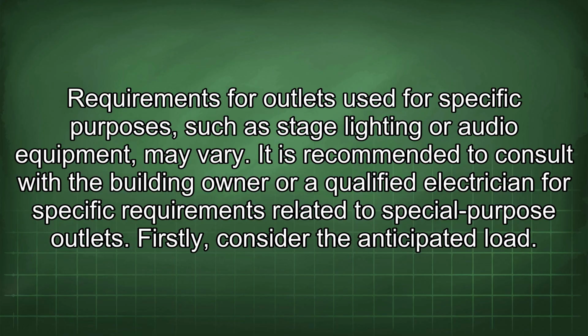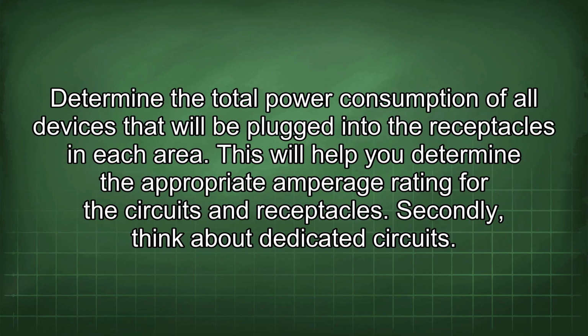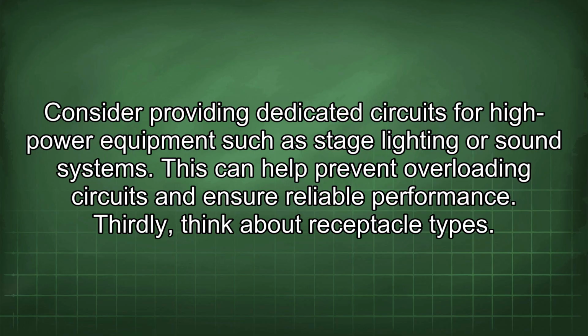Firstly, consider the anticipated load. Determine the total power consumption of all devices that will be plugged into the receptacles in each area. This will help you determine the appropriate amperage rating for the circuits and receptacles. Secondly, think about dedicated circuits. Consider providing dedicated circuits for high-power equipment such as stage lighting or sound systems. This can help prevent overloading circuits and ensure reliable performance.